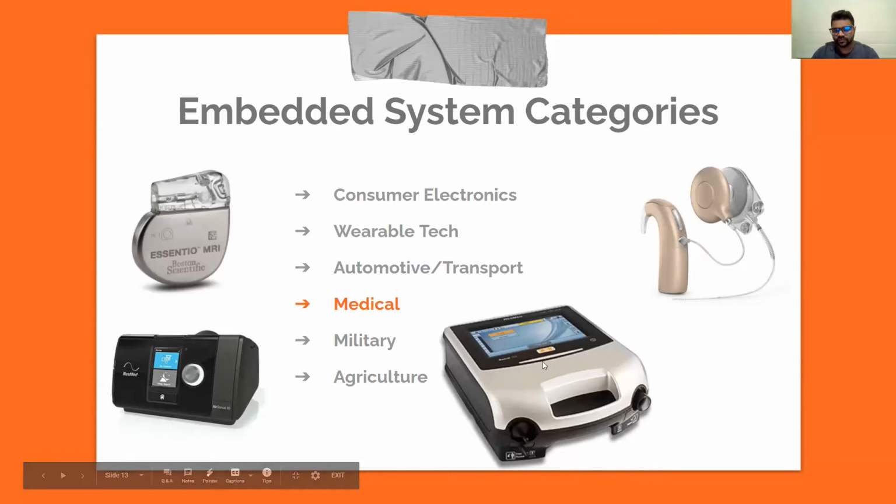ventilators. One of the arguments is that the standardization of these equipment is very high, because the moment one of these equipment fails, that means someone's going to die. So this is very critical, and because of that, we need to have so many redundant systems. We need to have alarming capabilities. Every single thing that we have in a circuit has a redundant component.